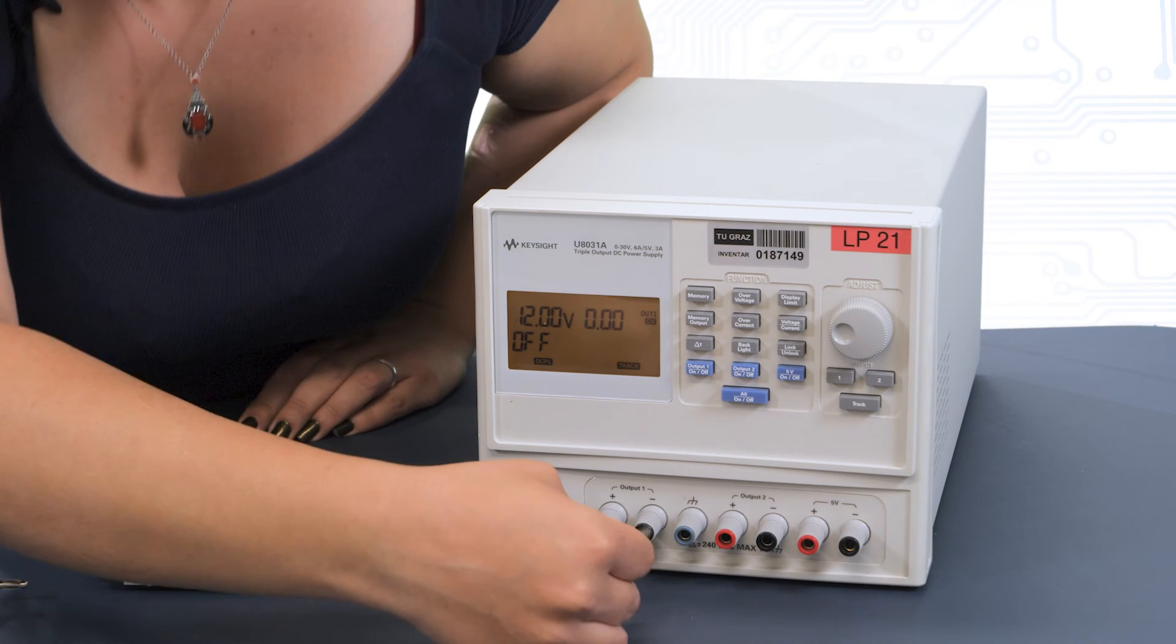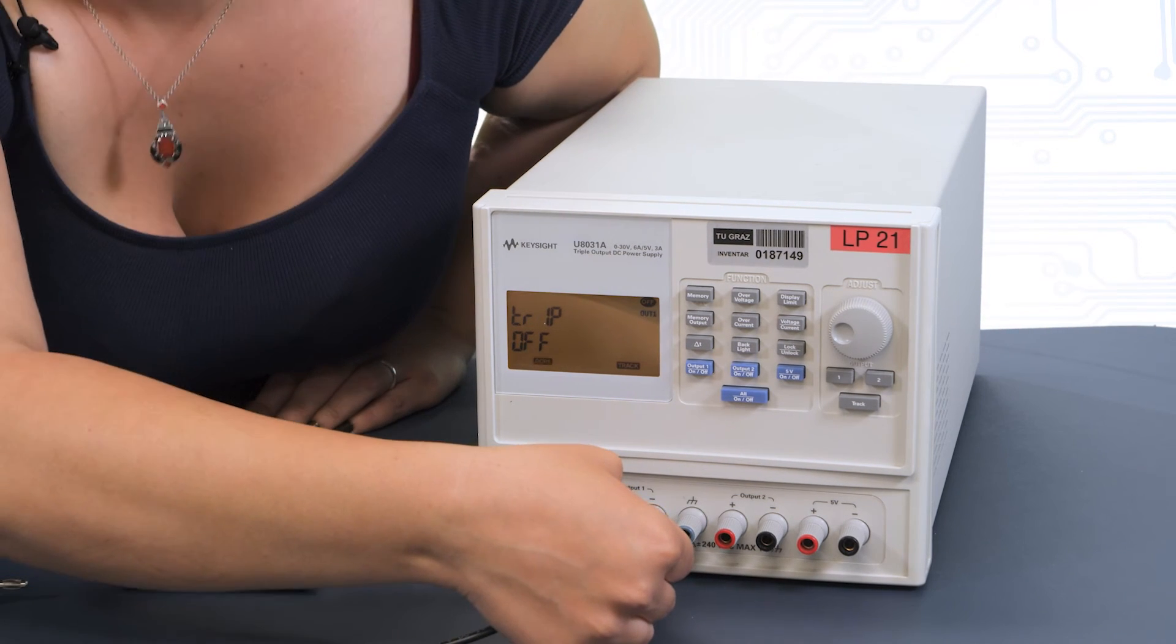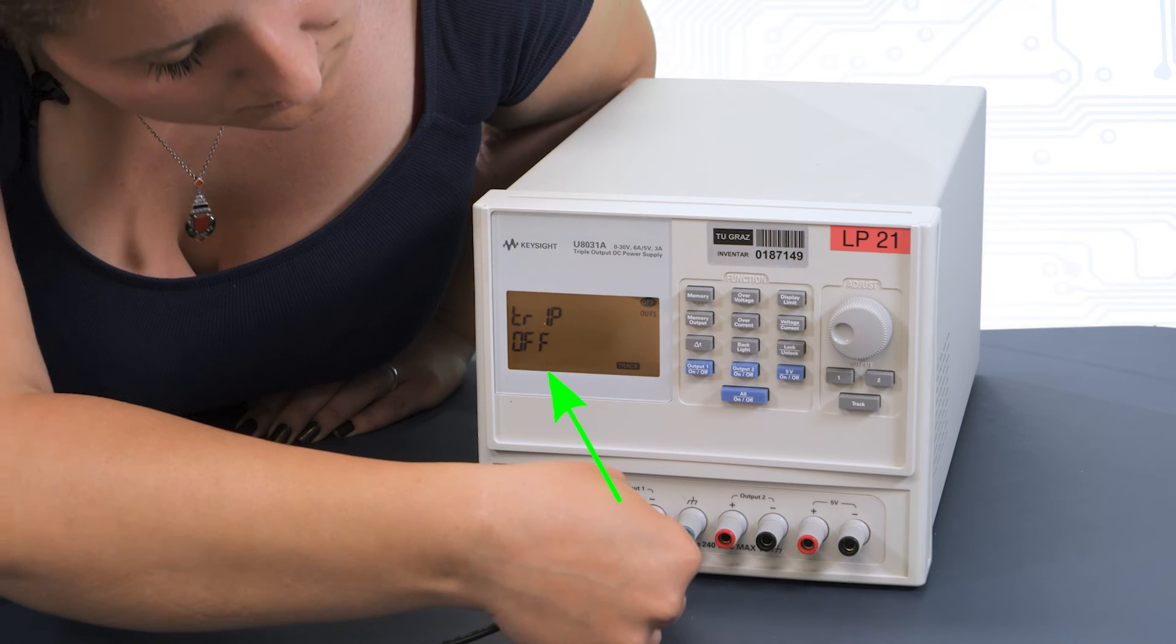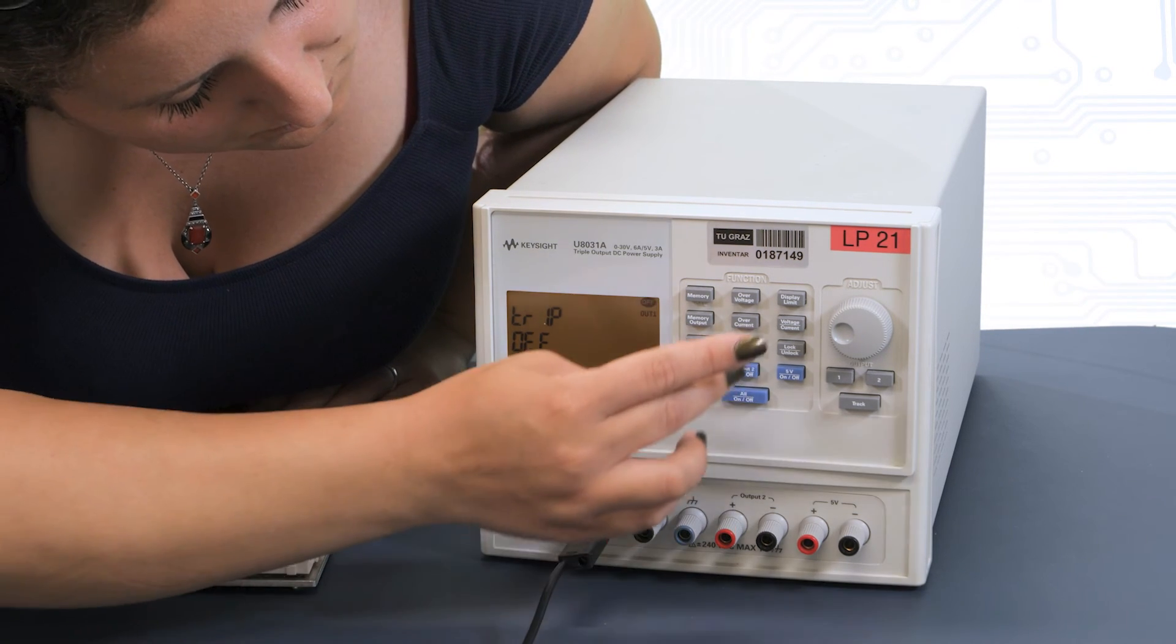But what happens with this function when the set current limit is reached? When this occurs, the corresponding output is disabled and an error is shown on the display, in this case TRIP. In addition, the OCP symbol blinks on the display. It should be mentioned that most other power supplies do not have such an option. These devices will limit the current as described before but will not deactivate the output.